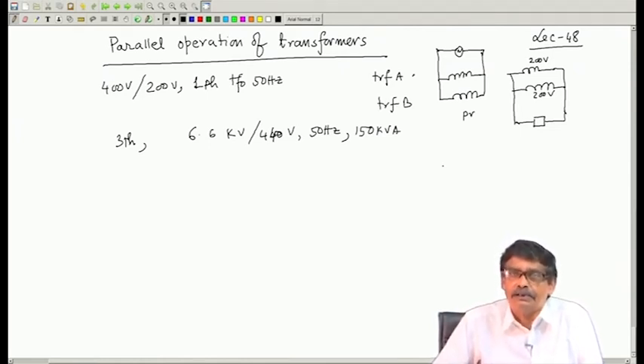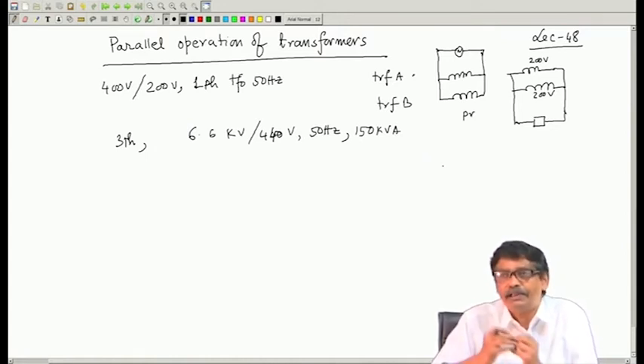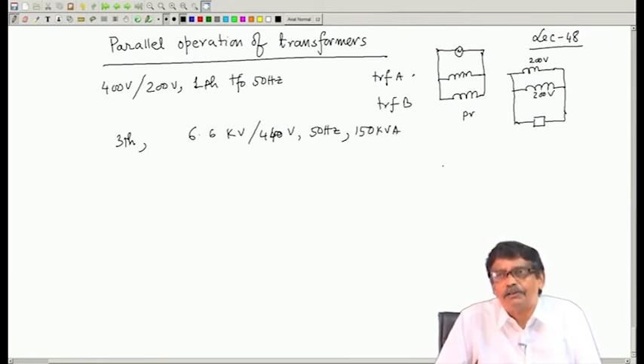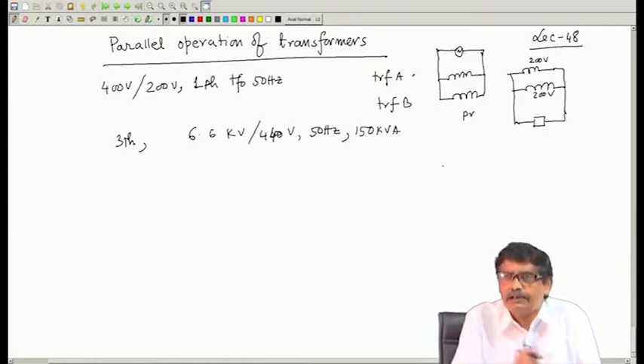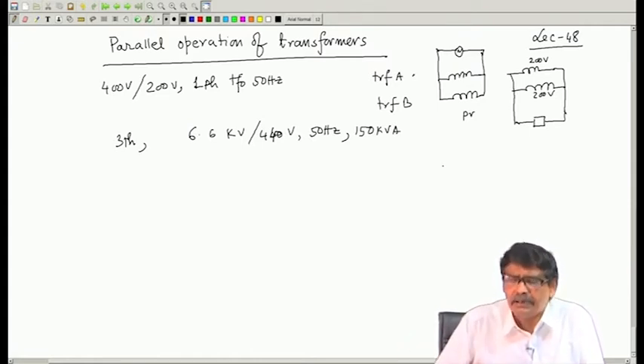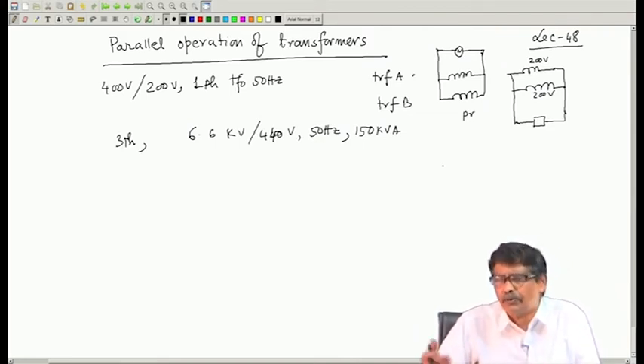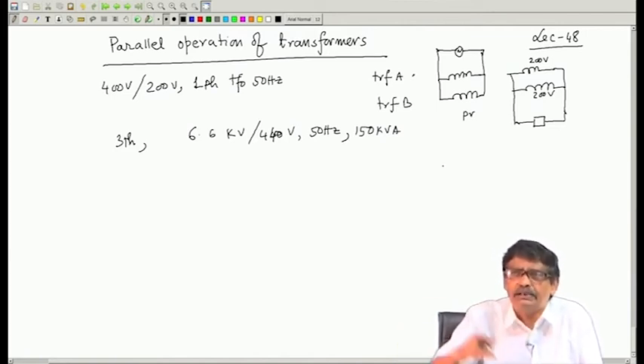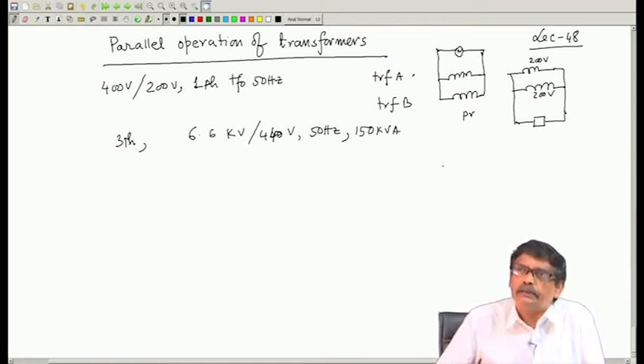I mean, in one case, if it is a single transformer, everything is blackout if that transformer develops a fault. But with more transformers in parallel, if one transformer goes out of order, you take it out, and then you can restore service, but not to all consumers, and you can rotate somehow to satisfy all the consumers by switching, disconnecting some consumers at some point of time and reconnecting some other consumers. So, these are the nice points of having, at least at the distribution level, some transformers operating in parallel.